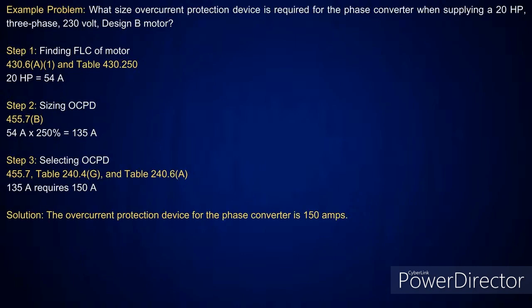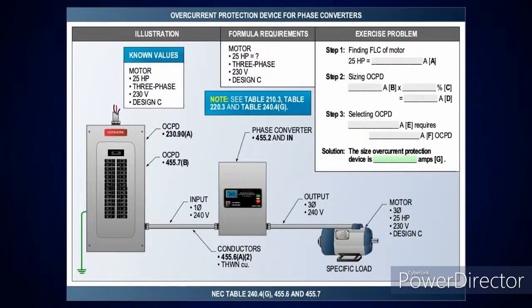And a lot of people will get hung up on an exam because they don't read past 240.4D. So you'll sit there and think, well, if I got to 240.4D, I can't even do any of this stuff. I don't even have permission to do any of this. But that's why you have to read down and make sure you read down to 240.4G, to make sure that whatever you're calculating is that specific conductor. Correct. And that's why we go through these and explain it step by step. And when you look at it, it's really not hard when you see the step procedures we put it in.